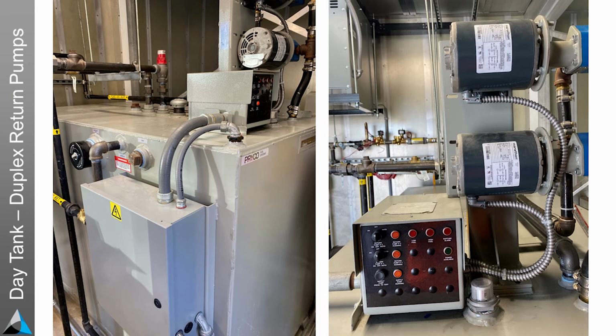This is the day tank for that generator. The interesting thing about this project is the fuel tank was down at the first level of the parking garage, and the generator is up about eight stories at the top of the parking garage. So that's why they have some extra redundancy on the supply pumps. But then here's your day tank in the generator enclosure with return pumps that, if the day tank gets too high, will return fuel back down to the main tank.